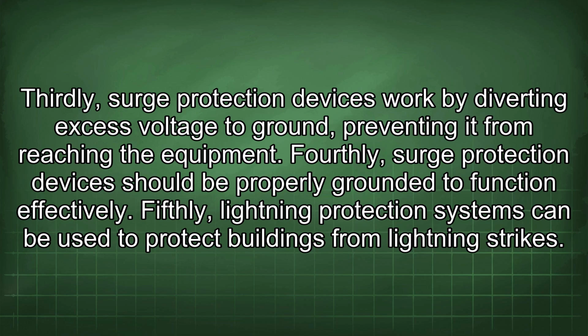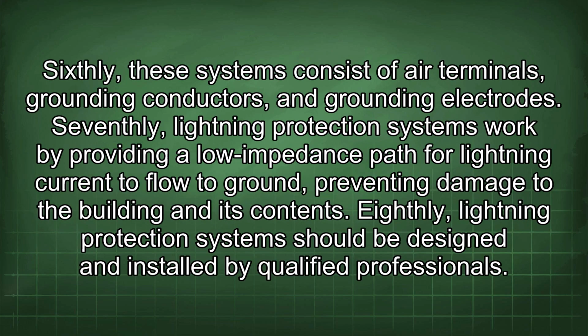Fourthly, surge protection devices should be properly grounded to function effectively. Fifthly, lightning protection systems can be used to protect buildings from lightning strikes. Sixthly, these systems consist of air terminals, grounding conductors, and grounding electrodes. Seventhly, lightning protection systems work by providing a low impedance path for lightning current to flow to ground, preventing damage to the building and its contents. Eighthly, lightning protection systems should be designed and installed by qualified professionals.